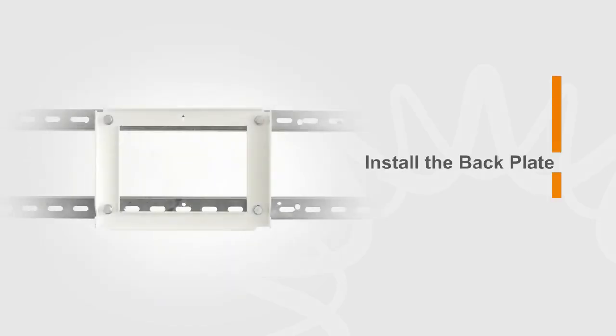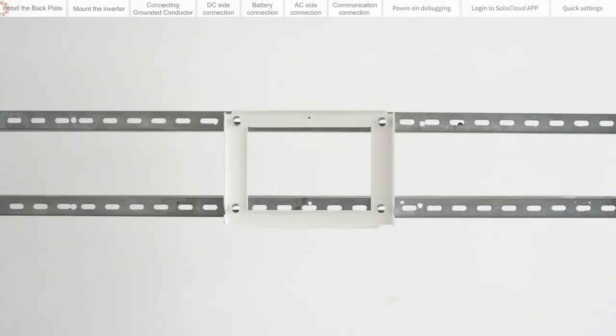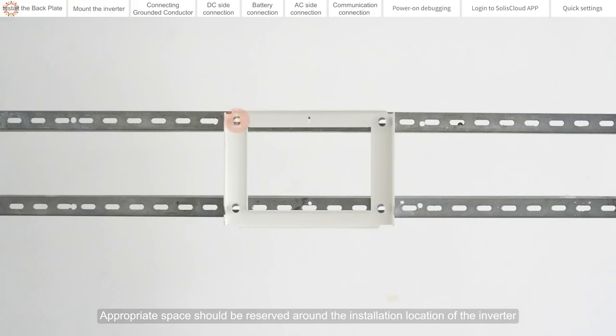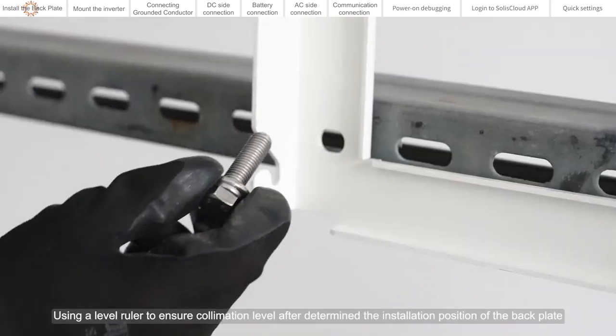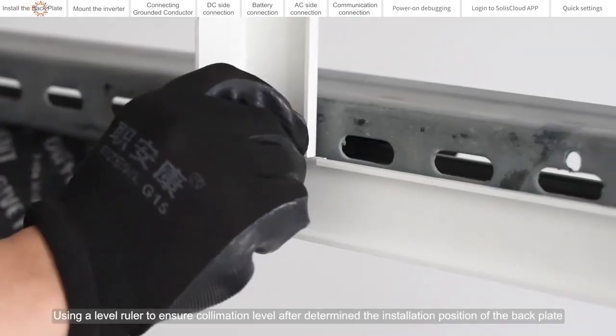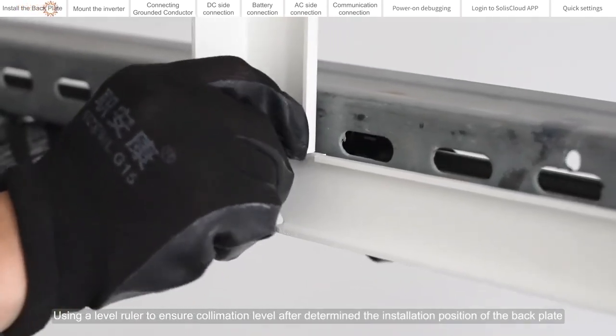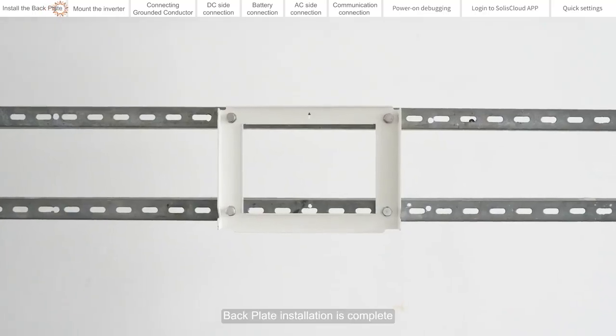Install the back plate. Appropriate space should be reserved around the installation location of the inverter. Using a level ruler to ensure collimation level after determining the installation position of the back plate. Back plate installation is complete.